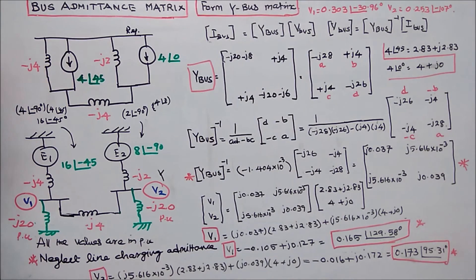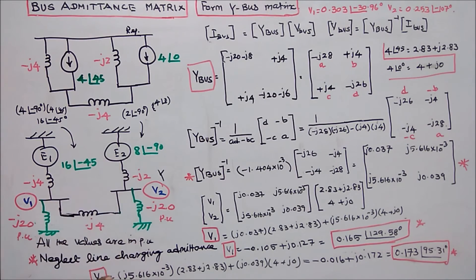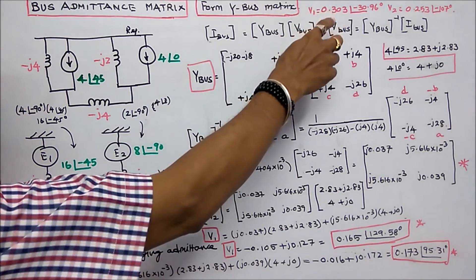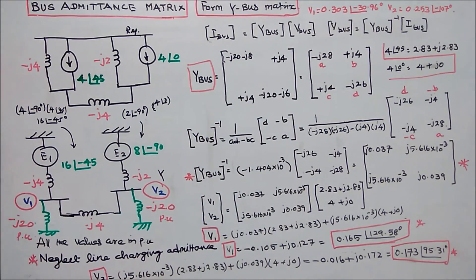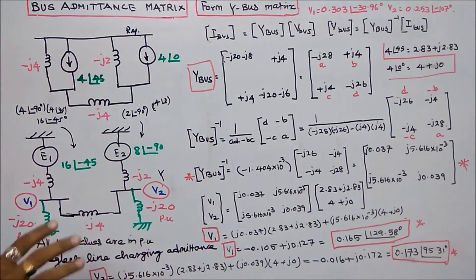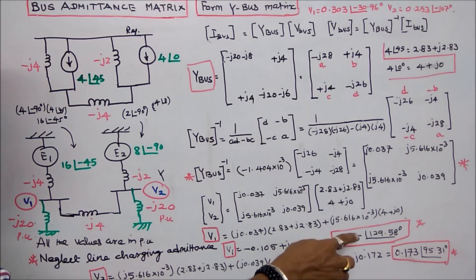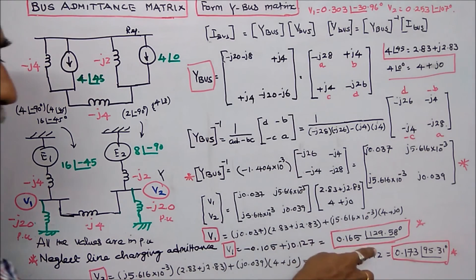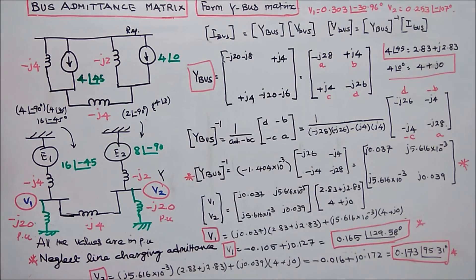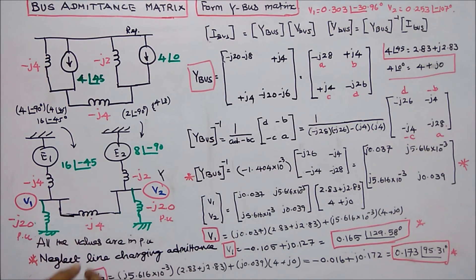Now we compare the results. In the first case with shunt capacitors (J20) at buses 1 and 2: V1 equals 0.303 angle minus 30.96 degrees and V2 equals 0.253 angle minus 107 degrees. In the second case with shunt reactors (minus J20): V1 equals 0.165 angle 129.58 degrees and V2 equals 0.173 angle 95.31 degrees. When adding shunt capacitors, the voltage magnitude is higher compared to the shunt reactor case. This is the key inference from this problem.